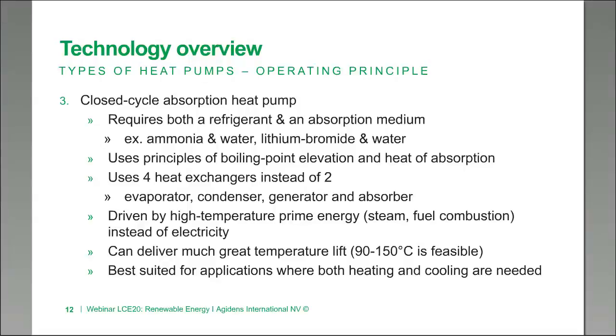The big advantage of absorption heat pumps is that they allow much greater temperature lift between source and destination side compared to regular compression heat pumps. For compression heat pumps you want to keep the temperature differential below 50 degrees, but with the absorption heat pump it is possible at times to raise the temperature by 90 or even up to 150 degrees. These applications are also well suited for situations where you need both heating and cooling.